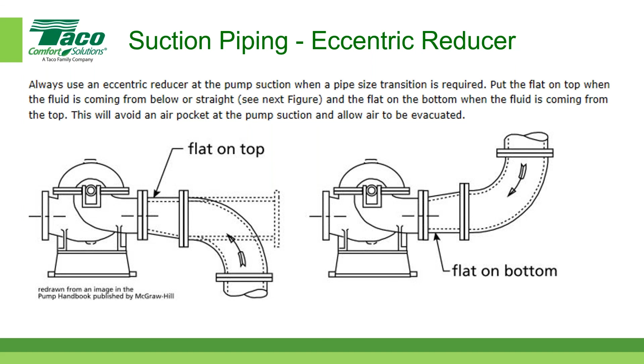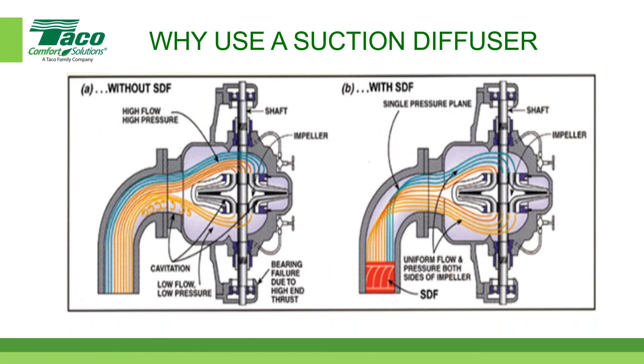Some ideas here. This is in our instruction sheets. Some piping thought processes there. It's very, very important for the types of pumps we're talking about today. Here's why you want to have that 5 to 10 pipe diameters, or use a suction diffuser, okay? This one has a suction diffuser, this one doesn't. If you get the incorrect flow, see how it jumps up here, you're getting higher flow and higher pressure, and this is low flow, and this could cause cavitation and all kinds of issues. Maybe the bearing might fail a lot quicker. So you want nice uniform flow coming in here, so you get equal amounts going to both sides. Very, very critical, very, very important. And you could do that with that piece of trim we're talking about, that suction diffuser.